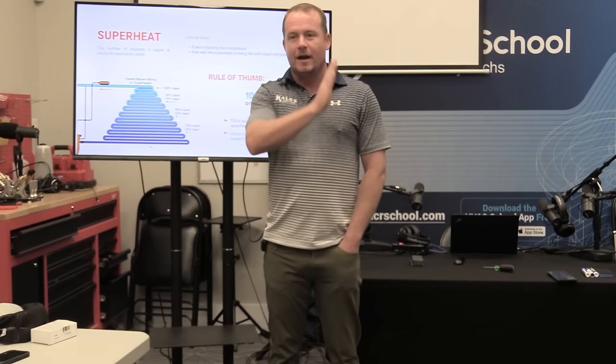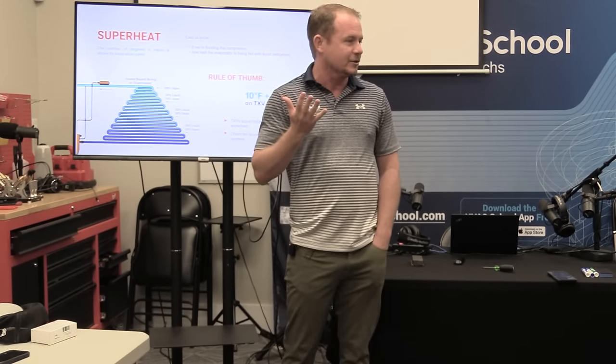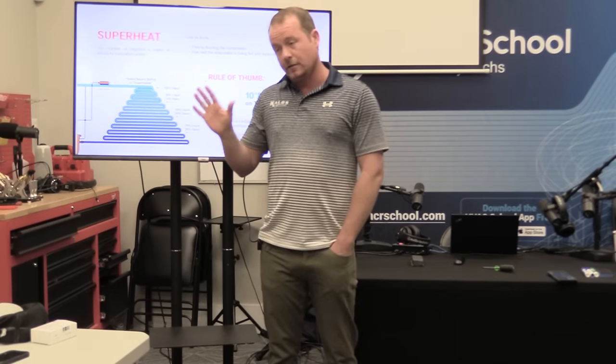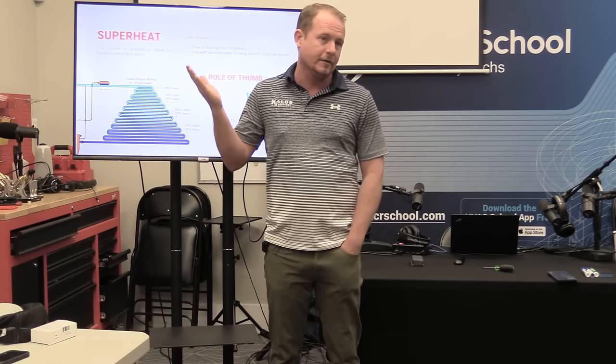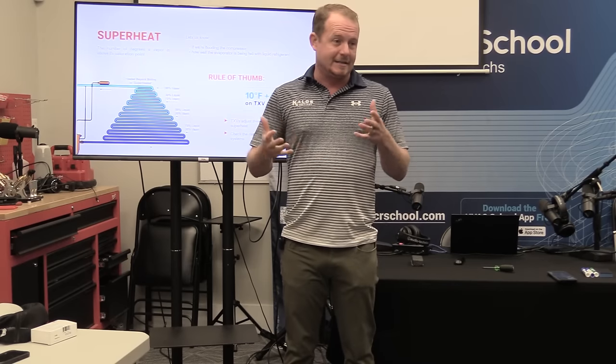Valves get misdiagnosed all the time because we don't check all the other stuff first. Do we have a temperature drop across our liquid line dryer? Do we have an airflow problem? Are we providing the valve with proper subcooling and proper liquid refrigerant? So we do all those things first, but we still monitor superheat. This frustrates me when I ask people how they check refrigerant charge on a TXV system and they just say subcool. You could hit the subcool number but have evaporator temperature off, superheat off, and CTOA off. If everything else is right — airflow, condenser airflow, valve operating properly — then yes, we set the charge by subcool.